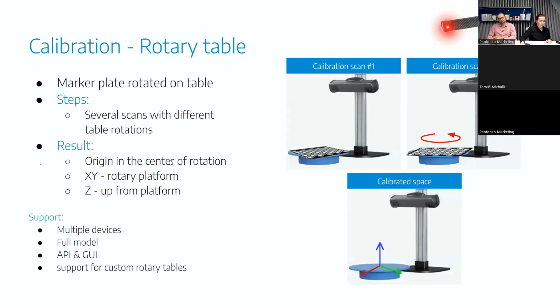Then there is the second approach, using the rotary table. In this setup, to calibrate it, the marker plate is rotated on the table. So we take a scan of the marker pattern in this position, then we rotate it slightly and take another scan. These two scans, and there can be several more of these scans, and also the recognized circles on the marker pattern are then used to calibrate the system. And the resulting calibration is that the origin or the coordinate system of this setup is moved to the center of the rotary platform, with the Z direction being up from the platform.